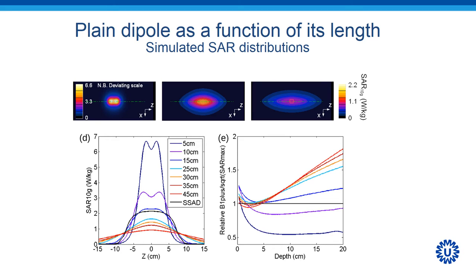An additional finding from this study is that these SAR peaks that you can see for very short antennas are associated with the conservative electric fields at the endings of a dipole, and these were the reasons that people were reluctant to use dipole antennas for MR imaging in the first place. However, we see that these SAR peaks actually disappear for longer antennas, and this is probably because the induced electric fields in the center become more dominant.